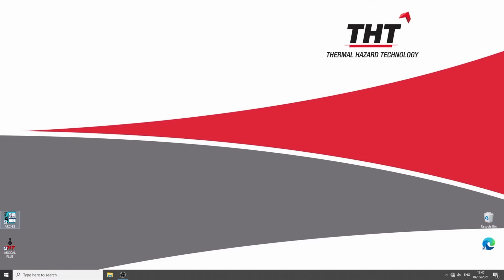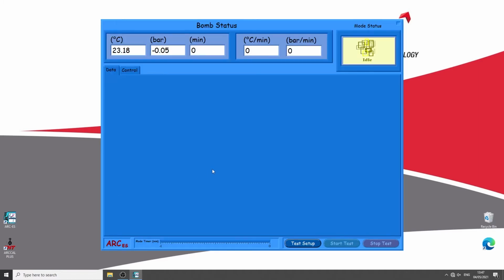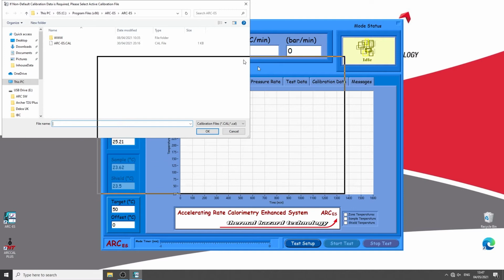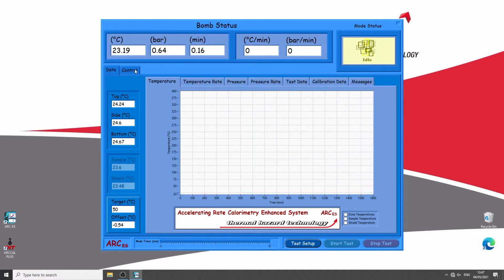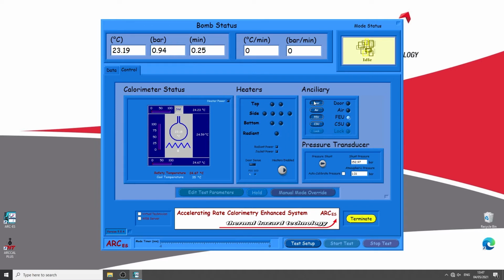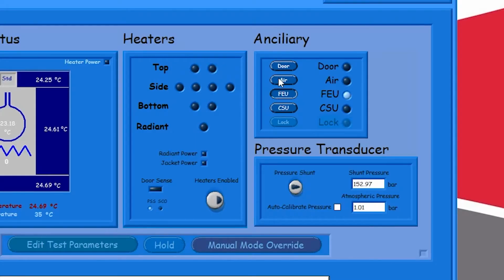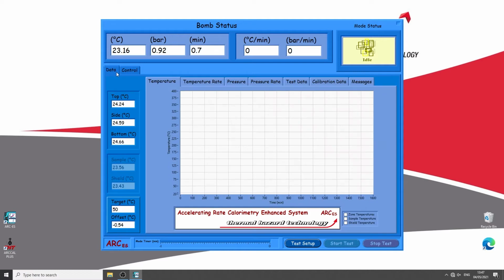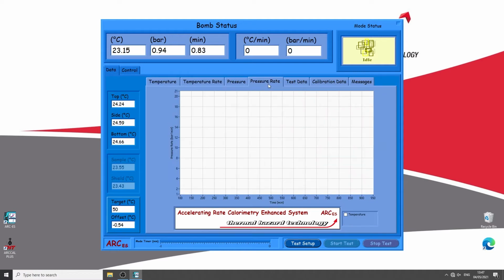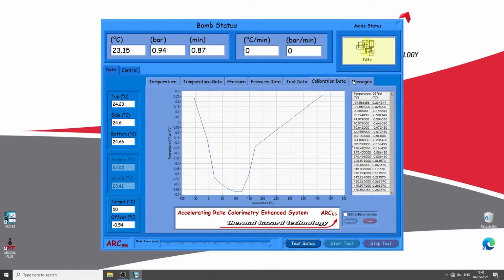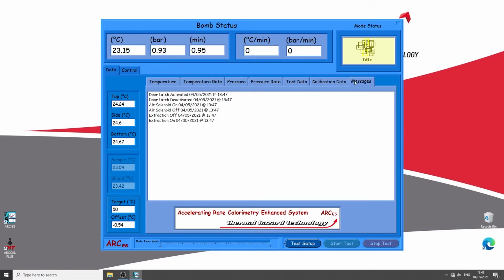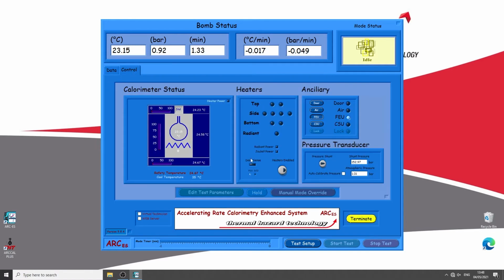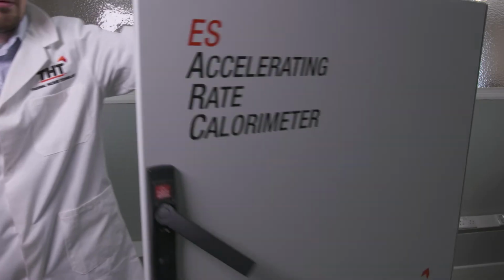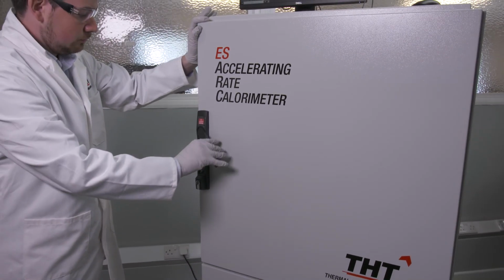Open the Arc ES software using the icon on the desktop. A dialog box will ask you to select a calibration file if required. In the Control tab, ancillary functions can be switched on and off: door lock, cooling air, fume extraction. Data is shown in the Data tab. Calibration data can be modified from the Calibration Data tab. The door sensor light will only come on when the instrument door is closed. If the door sensor is not on, the system will not heat.